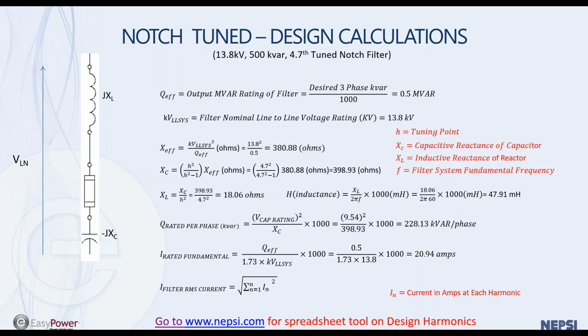And that starts off with this Q effective value here in the top left. I won't go through these equations one by one, but what's key is that once you design a harmonic filter, you have to look at the voltage on the capacitors, the current on the capacitors, and also the current on the reactors. We have a general rule of thumb that we design a filter such that the harmonic current does not exceed 50% of the fundamental current rating of the filter, and this is a key design concept. If you have a lot of harmonic producing loads within a facility, your reactor, X of L here, has to be able to handle that harmonic current. And the capacitor down here, per IEEE standard 18, also has to be able to handle that harmonic current. And there are limits on those values.